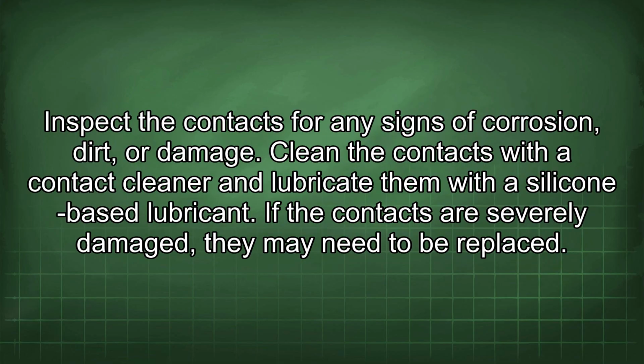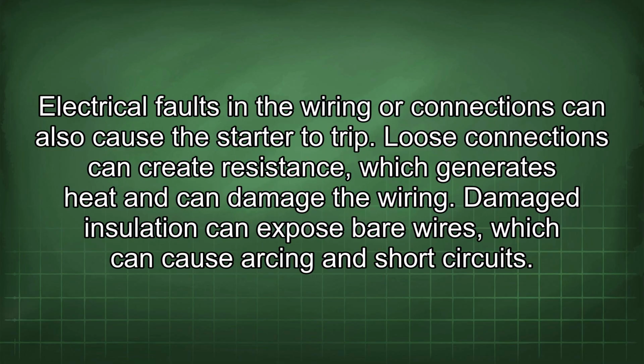Inspect the contacts for any signs of corrosion, dirt, or damage. Clean the contacts with a contact cleaner and lubricate them with a silicone-based lubricant. If the contacts are severely damaged, they may need to be replaced. Electrical faults in the wiring or connections can also cause the starter to trip. Loose connections can create resistance, which generates heat and can damage the wiring. Damaged insulation can expose bare wires, which can cause arcing and short circuits.